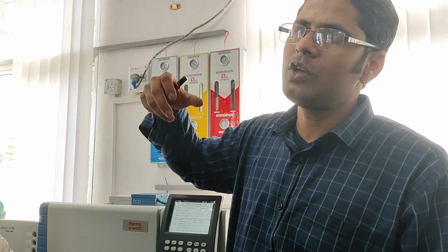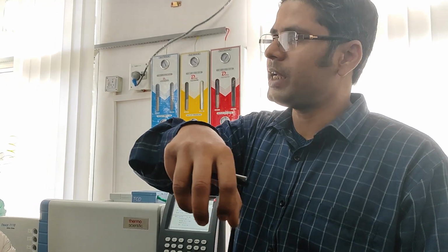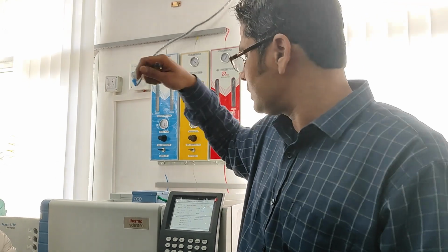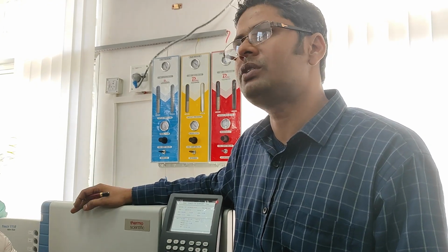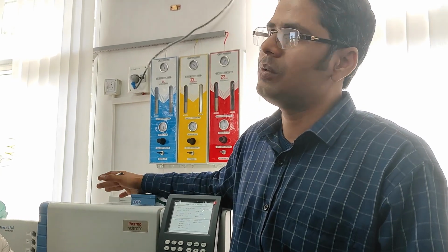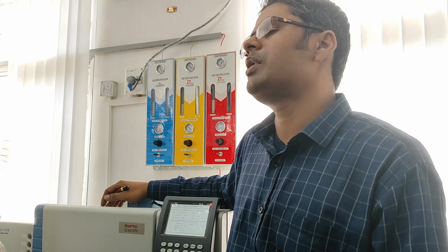The dissolved gas is extracted from this liquid, and that gas is injected into the GC to check whether acetylene, hydrogen, or combustible gases are present. If they are, that means within a few months that transformer may blast. So they regularly check with the GC system. This is called DGA, dissolved gas analyzer, and that GC will be named DGA.